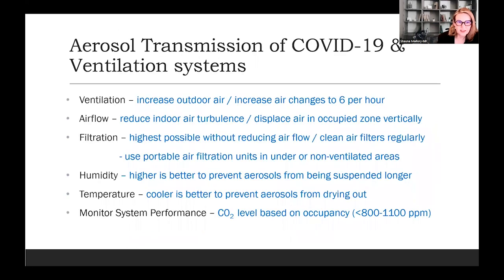So in conclusion, on ventilation: increase your outdoor air, increase air changes if you can, and reduce indoor air turbulence. If you're going to open a window and you have a fan, point it out, don't point it into the room. If you can, displace air vertically towards the mechanical exhaust. Filtration: use the highest possible without reducing airflow. Clean your filters regularly. Use your portable air filtration units in under or non-ventilated areas. Higher humidity is better. Cooler temperatures are better. And monitor the system performance. You can use CO2, and look for anything over 800 to 1100 parts per million as a starting point for concern. That's it.